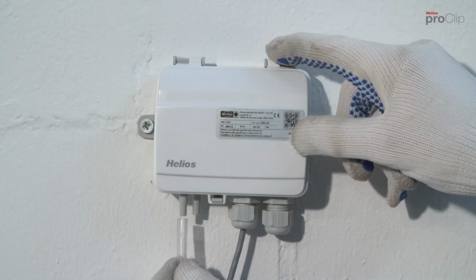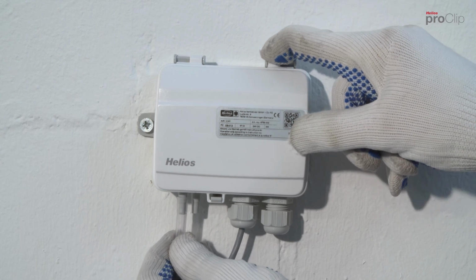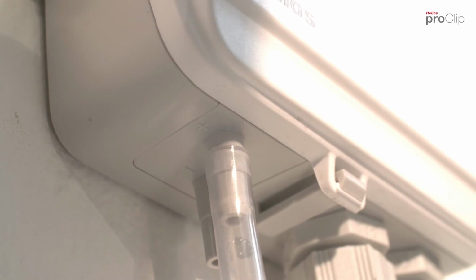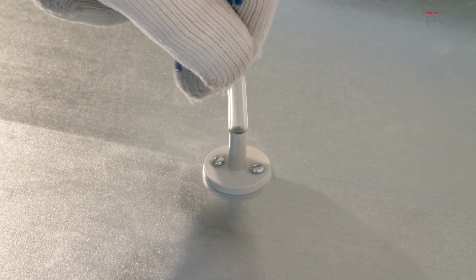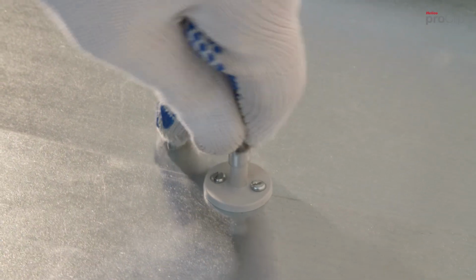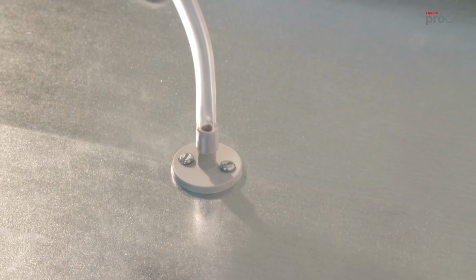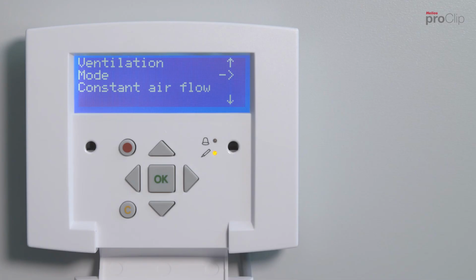The next step is to connect the supplied pressure tube to the pressure input P1+ on the cap pressure sensor and the measurement probe on the ventilation duct. This completes the installation process. The cap pressure sensor is activated in the Commissioning Assistant. To do this, click on one of these 2 preview videos.